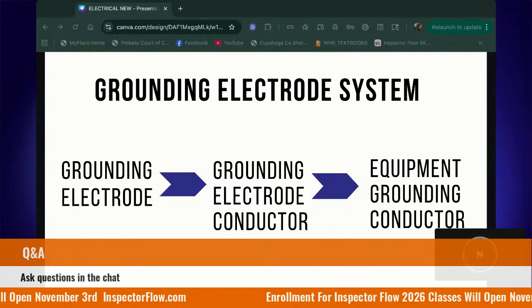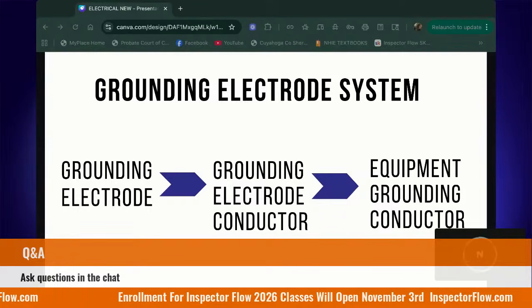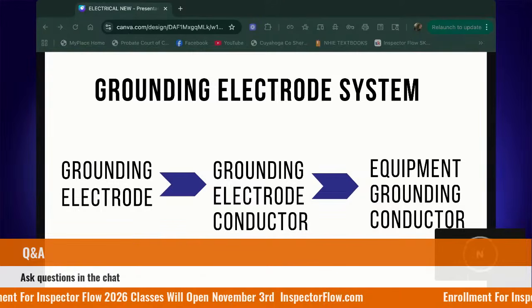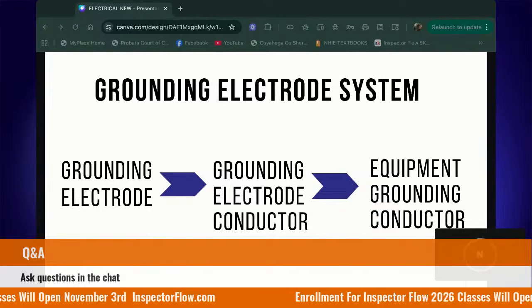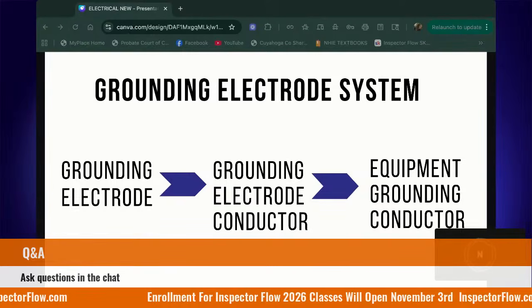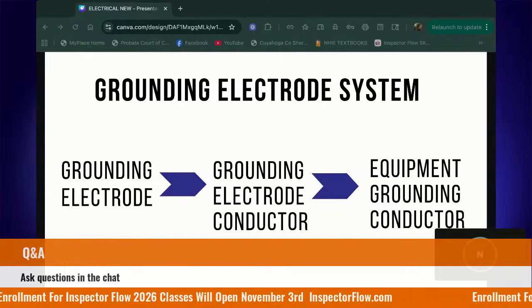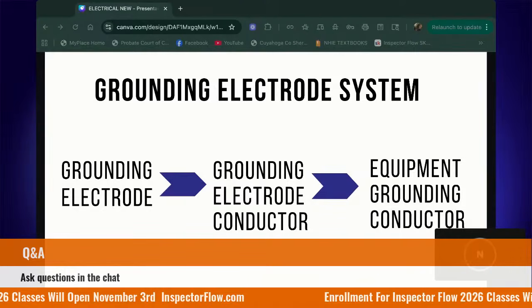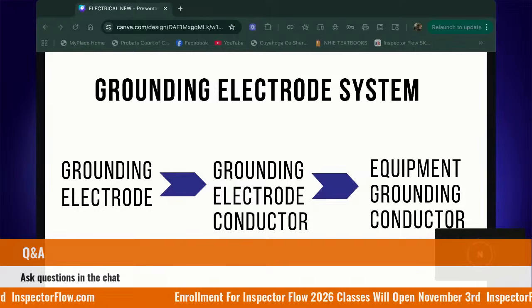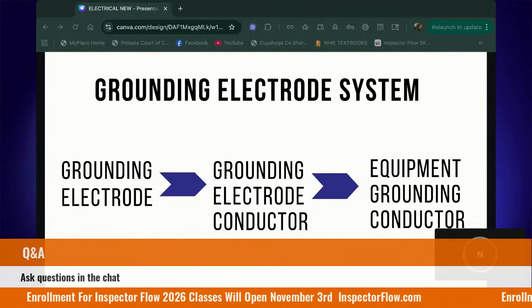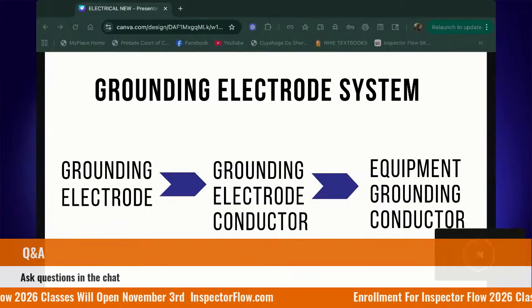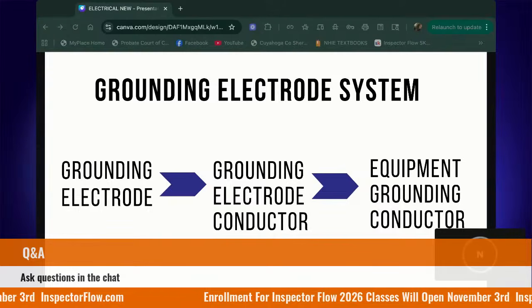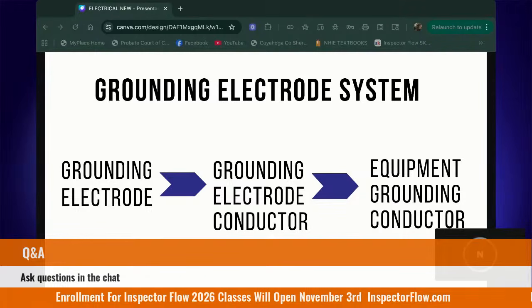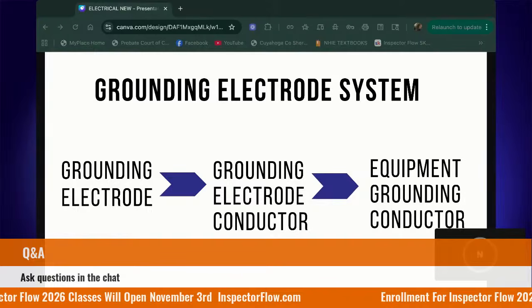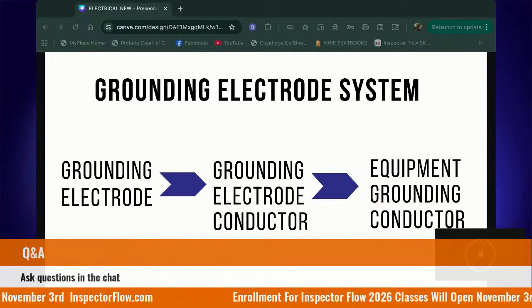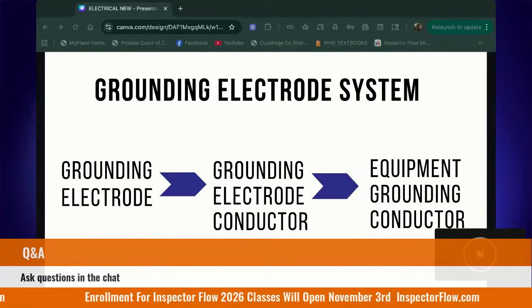If this wire is loose, if it's not properly attached at the lug, if it's corroded, if it's missing, then we break a link in our grounding system chain. How would the current get from the panel outside to the ground or to the GE, lest we have a GEC? And then lastly, the EGC, or the equipment grounding conductor. This is the green or bare copper wire inside of our branch circuits. These are the wires that connect every outlet, every switch box and every metal fixture back to the grounding system.